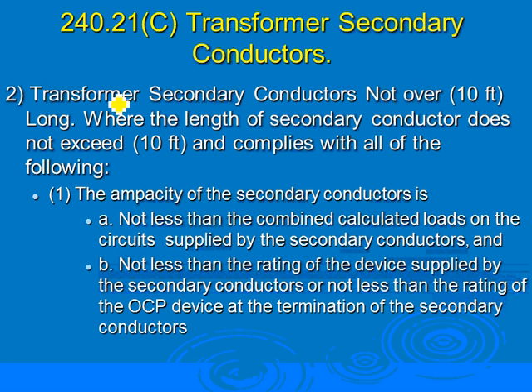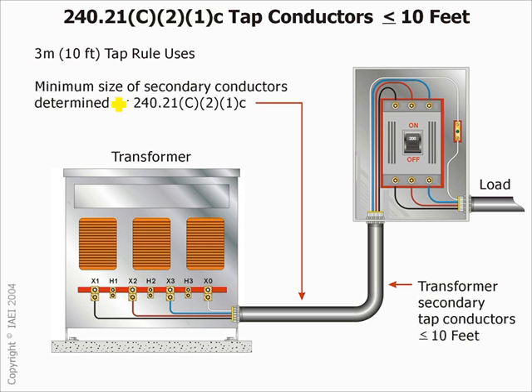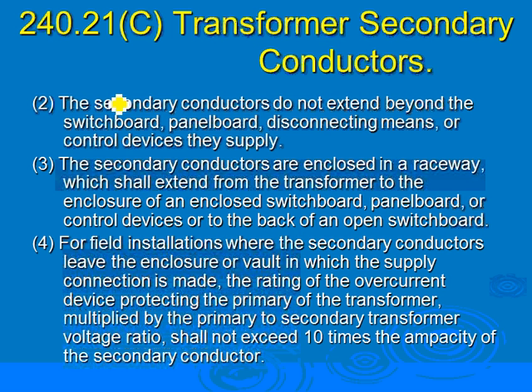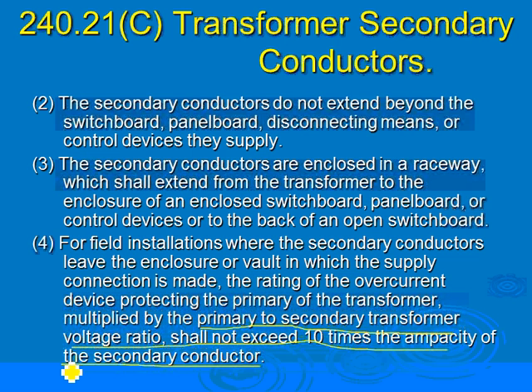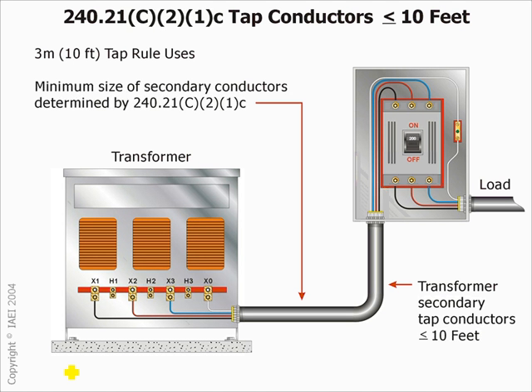Okay, so we talked about the 10-foot rule, guys, for the transformers. Transformer secondary tap conductors cannot be more than the 10-foot rule, but you have to make sure that 10 times shall not exceed the ratio. Here's the primary to secondary ratio that we just talked about, and we converted them. The primary to secondary ratio. So 10 feet.